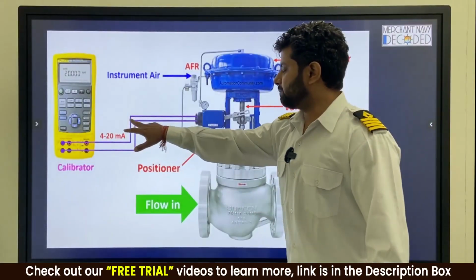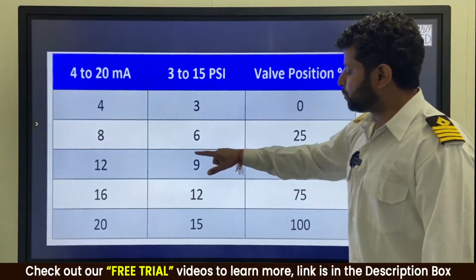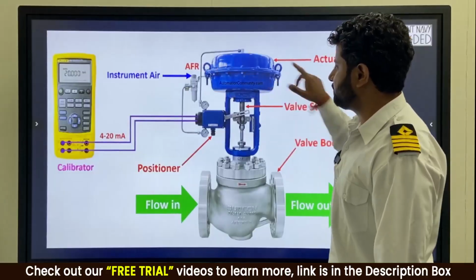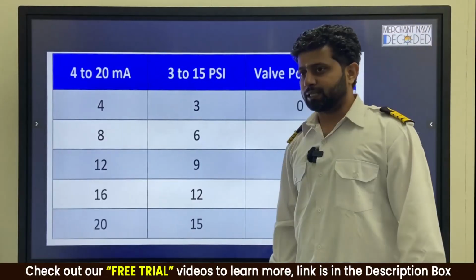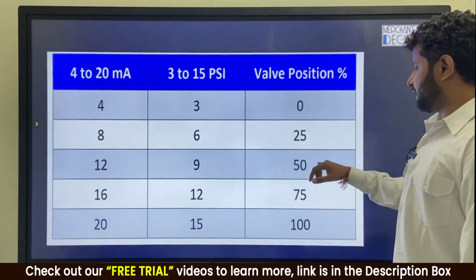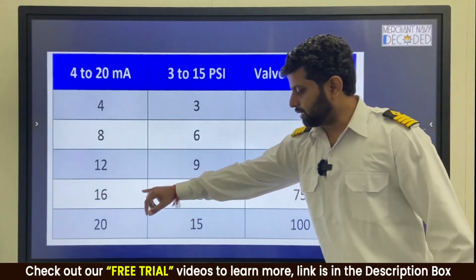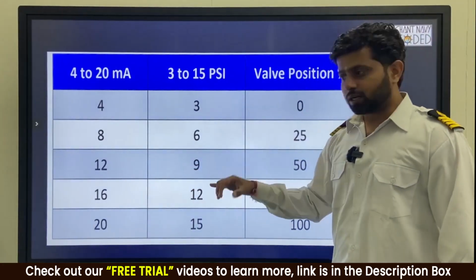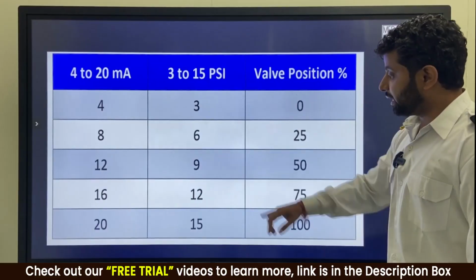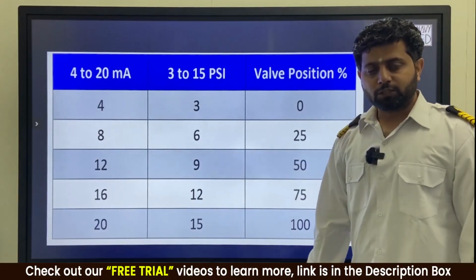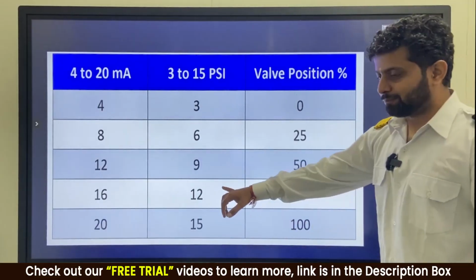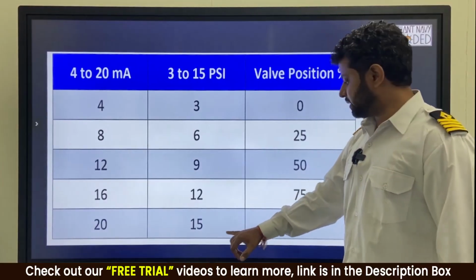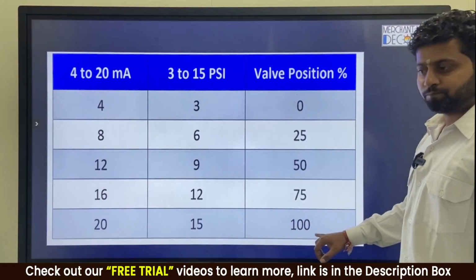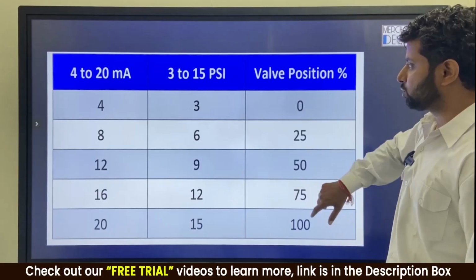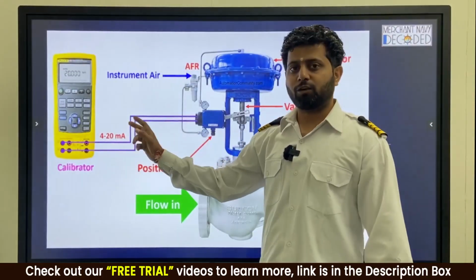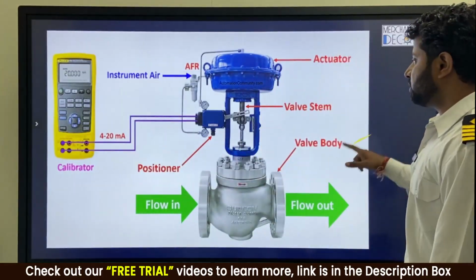When the same current becomes 12 milliamps, the output air signal coming over here will become 9 psi, around 0.6 bar, and valve will be 50% open. Then 16 milliamps, then the air output coming out will be 12 psi, which will be around 0.8 bar, and finally 1 bar over here when the valve will be 100% open. And who is deciding that valve to open or close? Just a small current signal of 4 to 20 milliamps. So this is how a IP converter works.